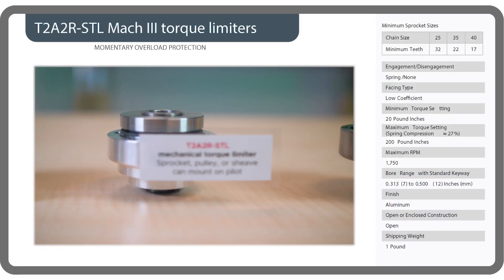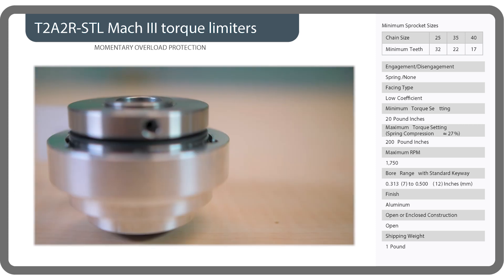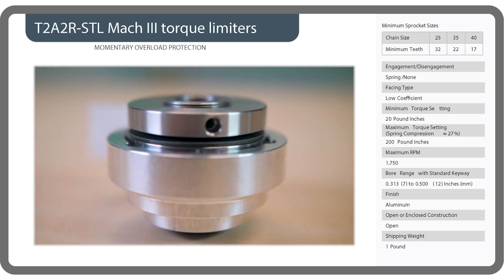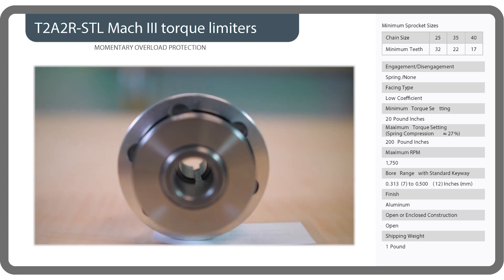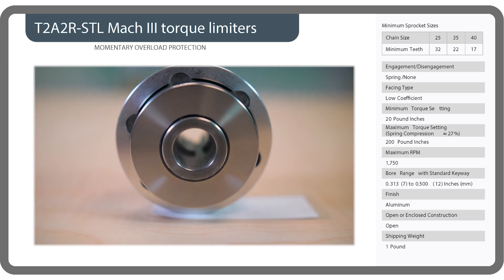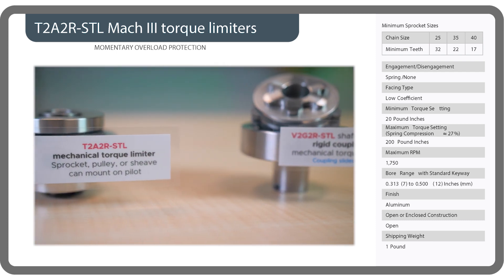Let's check out our first sample: a T2A2R STL mechanical torque limiter on which a sprocket, pulley, or sheave can mount. This is a spring-engaged design having low coefficient friction discs. Minimum torque is 20 pound inches and maximum torque with 27% spring compression is 200 pound inches. This one-pound torque limiter works on axes with speeds to 1750 RPM. Torque limiters can integrate into motion systems in a few ways — this one accepts input via sprocket and chain or pulley and belt assembly.